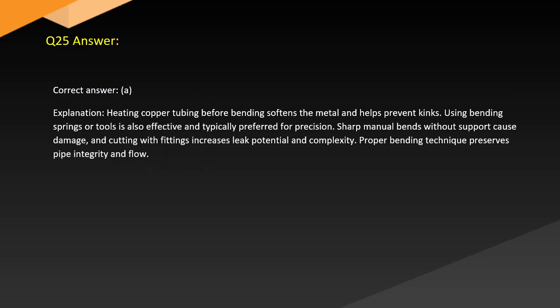Answer. Correct answer, A. Explanation. Heating copper tubing before bending softens the metal and helps prevent kinks. Using bending springs or tools is also effective and typically preferred for precision. Sharp manual bends without support cause damage, and cutting and rejoining with fittings increases leak potential and complexity. Proper bending technique preserves pipe integrity and flow.